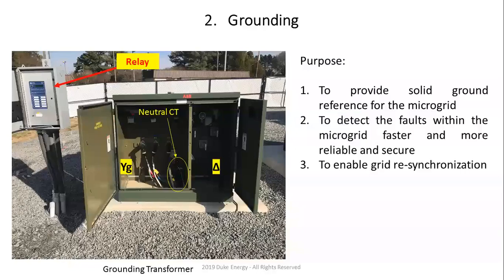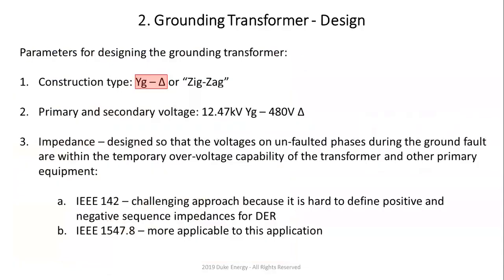The reason why is that if you open this grounding transformer before you close the PCC, your PCC 25 settings, which are sync check settings, won't be able to see the right values because you have removed the source of grounding. So the grounding transformer is probably one of the most complicated things to design in the microgrid. This is my personal experience. I can tell you I have designed a lot of things within the microgrid.